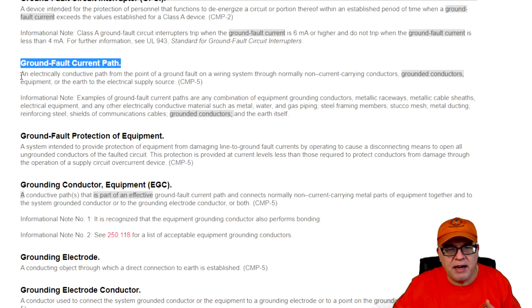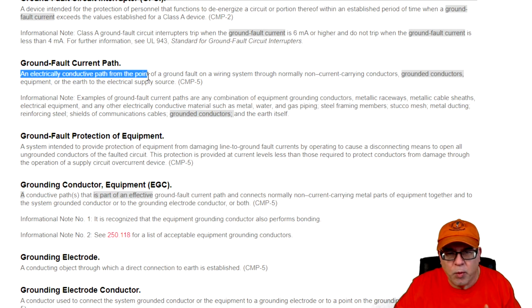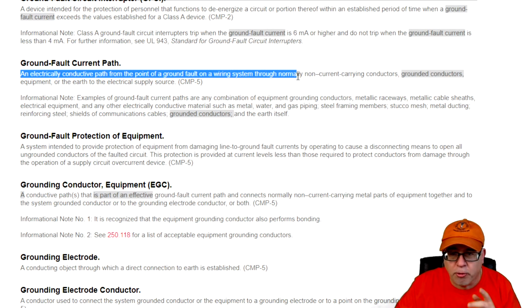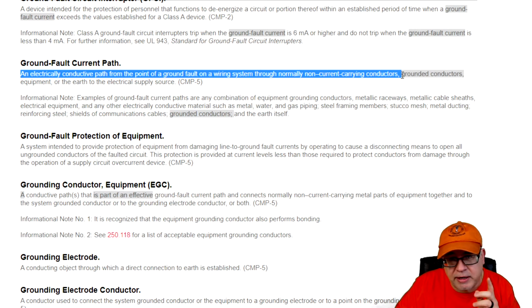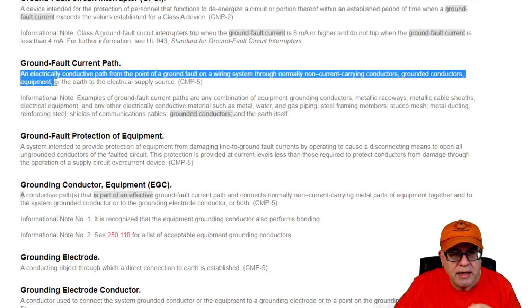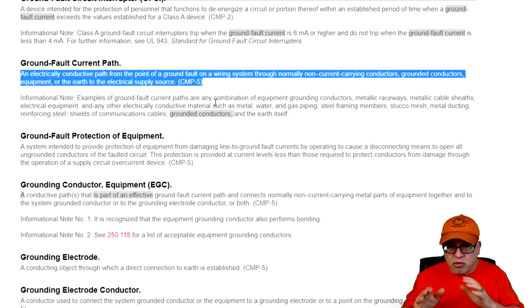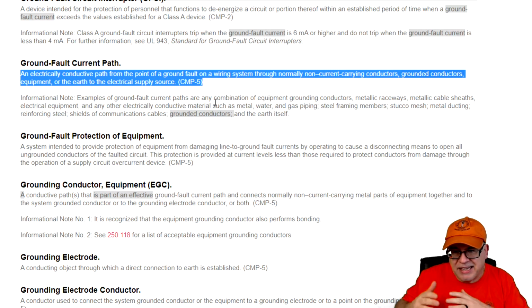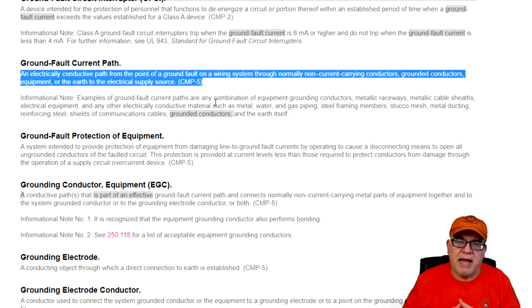Now, it's an electrically conductive path from the point of a ground fault on a wiring system through normally non-current carrying conductors, like equipment grounding conductors and whatnot, grounded conductors, okay, and equipment, or the earth to the electrical supply source. Remembering, for example, you can never use the earth as a path, okay? It's really not supposed to do that, but it can and will serve as a path. And you hear the old saying that electricity takes the path of least resistance. All right, well, for years everybody says that's not true. Well, it's not, in a sense.